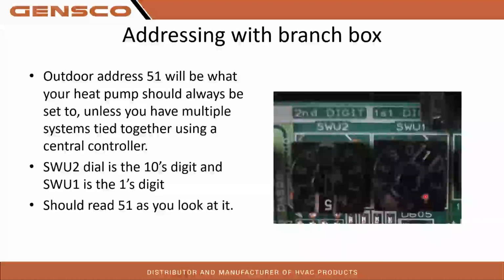The only time this is going to change is if you have multiple systems tied together. So they have maybe a central controller or some BACnet controls that they're doing where they want to be able to run both systems off of one place. Then they tie it together and you'd have to do a little bit of different addressing with your second unit. If you guys get into that situation, I just encourage you to give us a call. We'll walk you through it. We'll show you how to set that up. It's really not hard, but it can be confusing for the first time. But like I said, for the most part, I'd say for 99% of your installs, this right here is how you're gonna set those address dials on your heat pump.